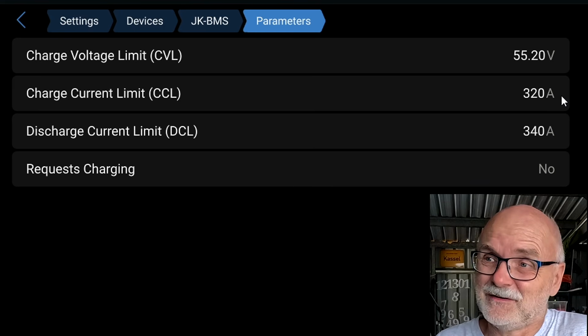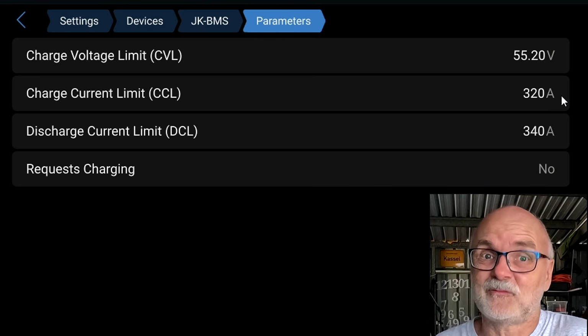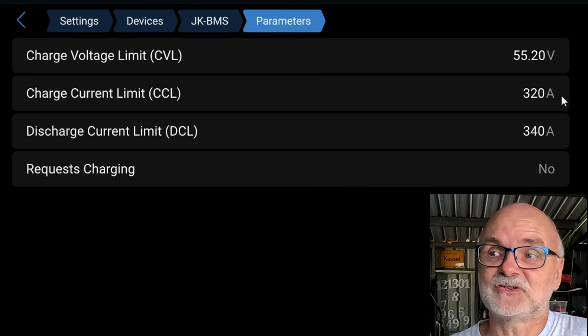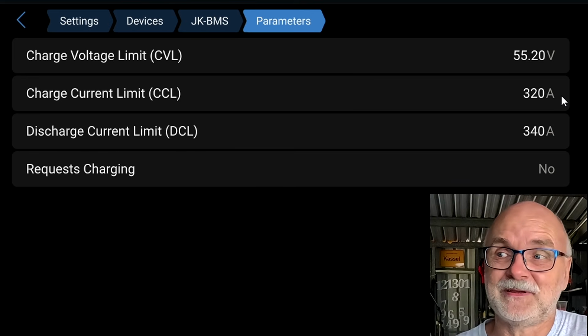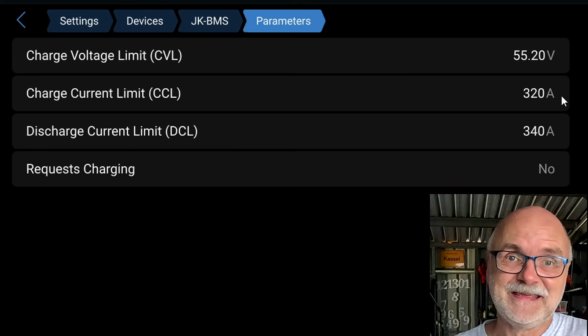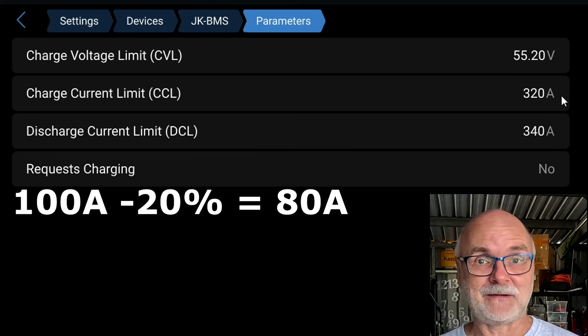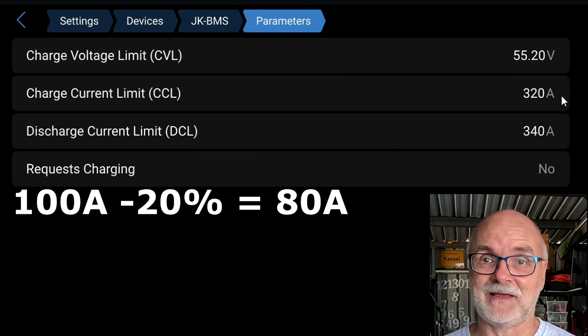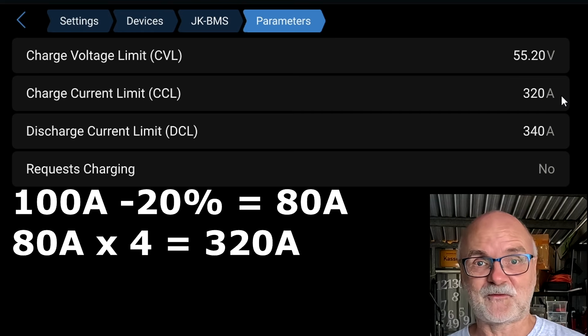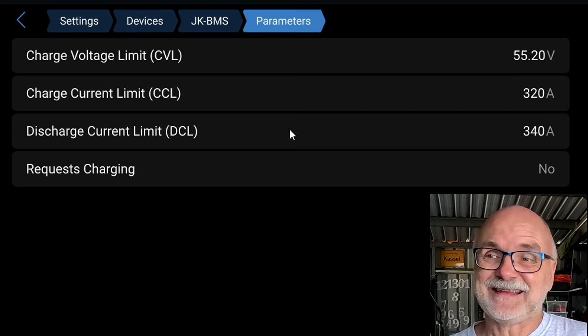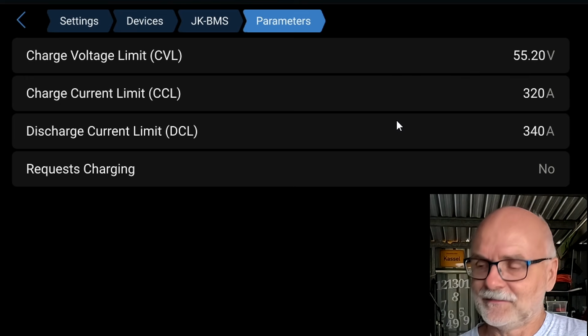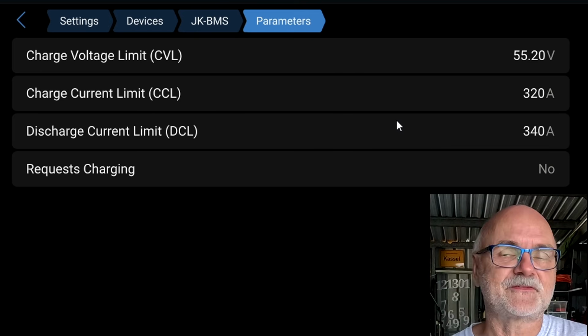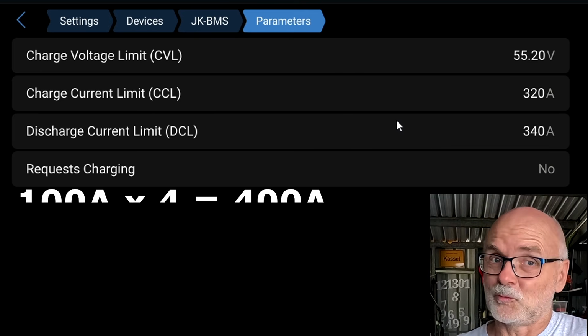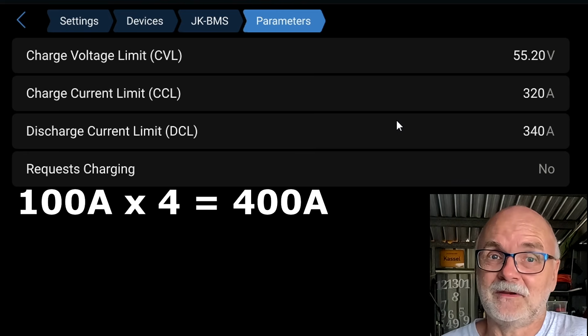So why not 400? 100 amps per battery times 4, because the JK-Inverter BMS takes 20% off whatever you are setting here in the app. So 100 amps minus 20% is 80 amps. So it requests only 80 amps per BMS, and 80 amps times 4 is 320. It does a similar thing for the DCL, the discharge current limit. This is the continuous discharge current setting in your app, which sits on 100 amps as well. So 4 times 100 is 400.